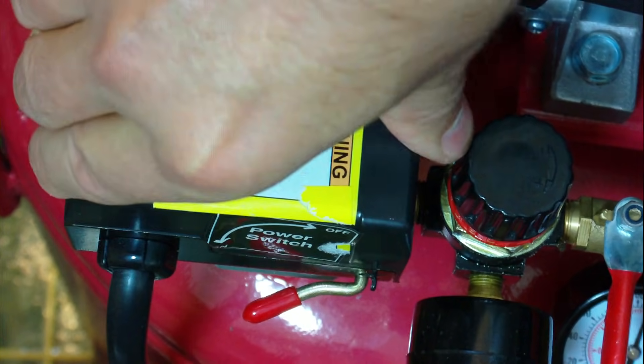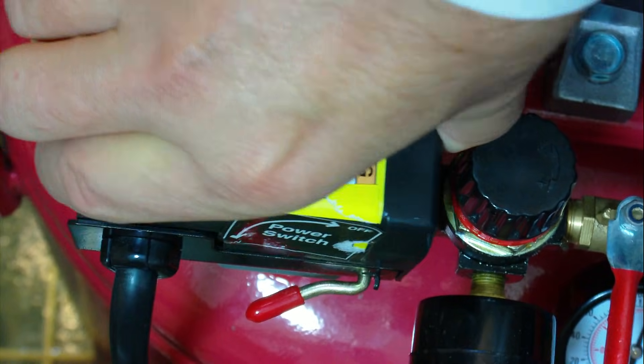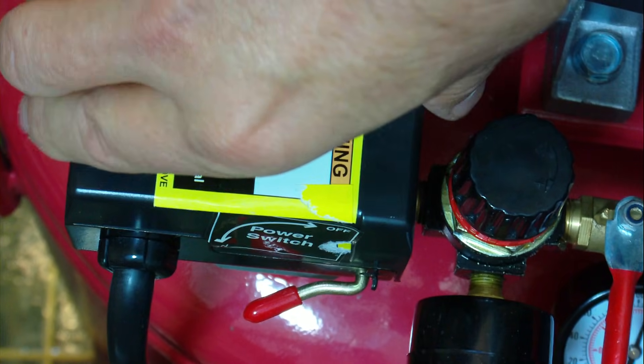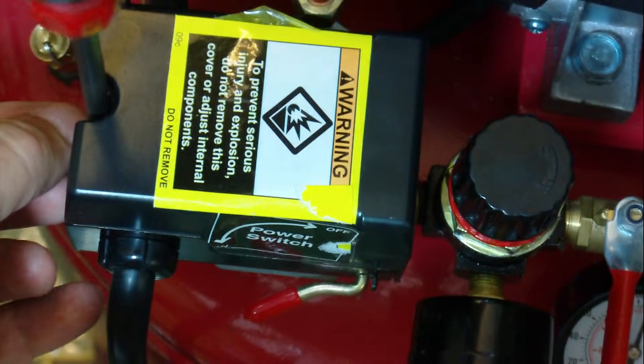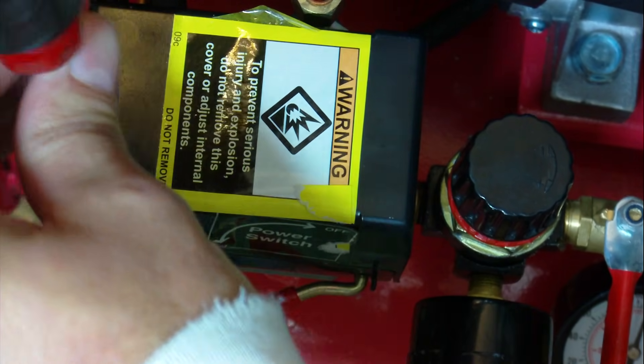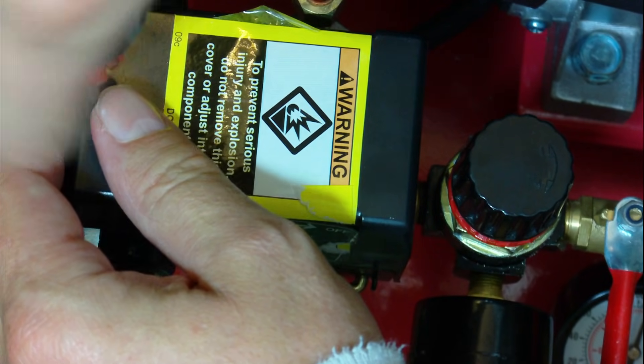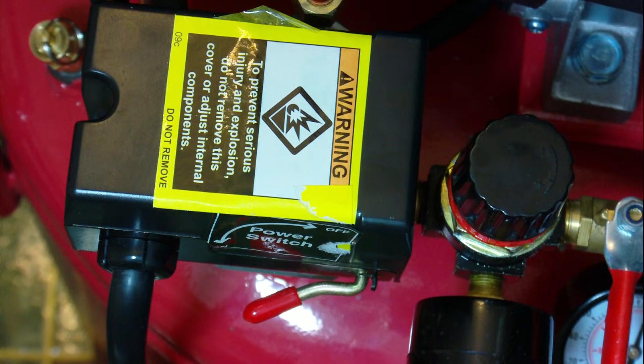To put this on you just set it back on here. Keep in mind it's got this tab that clicks on. You hear that click? Now I can hardly get it off. This is kind of hard to get off, and that's why I say take the power off it before you stick your finger in there and get shocked — it'll look like Einstein with a bad hair day. Just put this little bitty screw in here and tighten it up using just your fingertips. Don't put any force on it because it's just a little bitty screw — if you put much pressure on it you're going to strip it. And that's all there is to setting the pressure up on one of these.